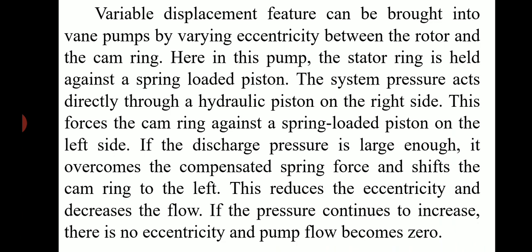Here in this pump, the stator ring is held against a spring-loaded piston. The system pressure acts directly through a hydraulic piston on the right side. This forces the cam ring against a spring-loaded piston on the left side.